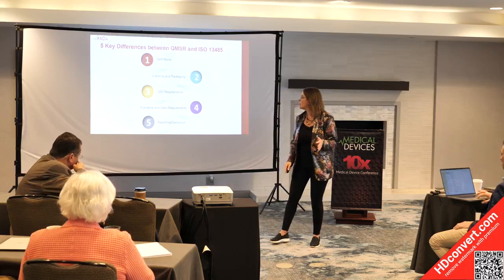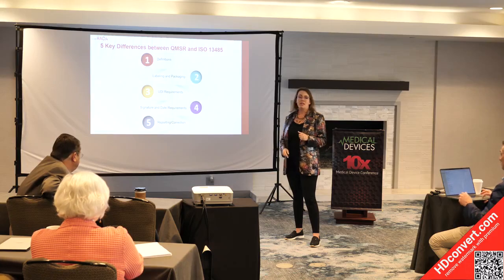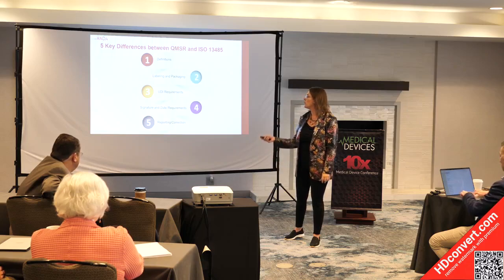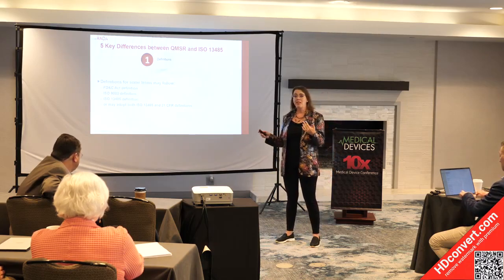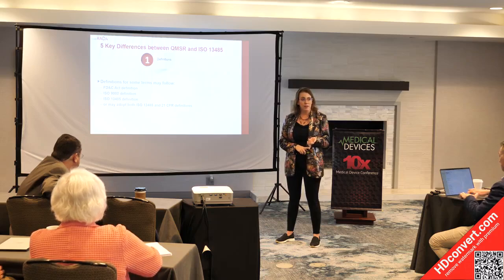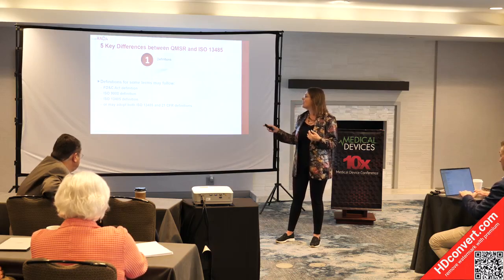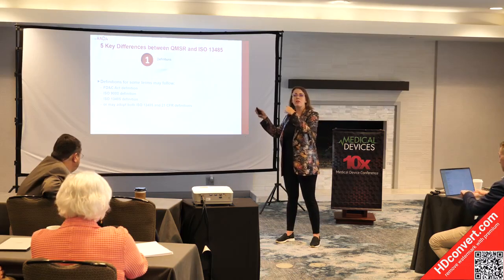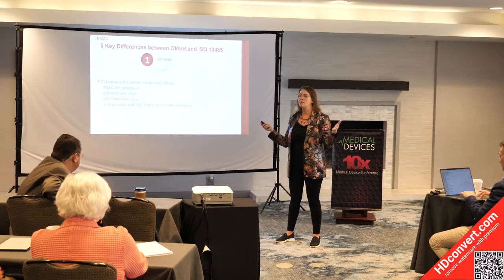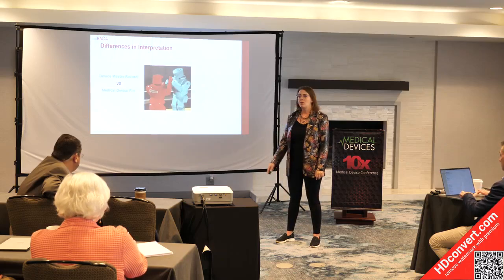The five big key differences are: definitions, labeling and packaging, UDI, signature and date requirements, and the concept of reporting, correction, and removal in the US. On definitions, it's more than just semantics — you have to consider the FD&C Act, which sometimes takes precedence over the ISO 13485 and ISO 9000 definitions. There are also other 21 CFRs where those definitions may take precedence, and sometimes both apply.